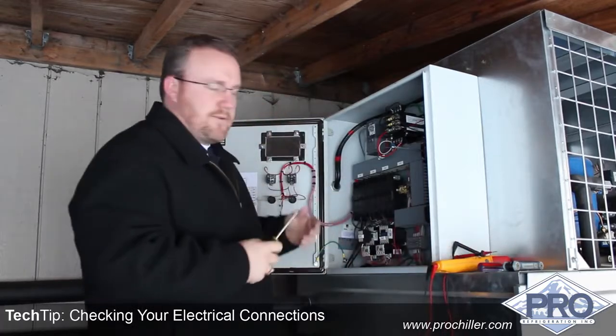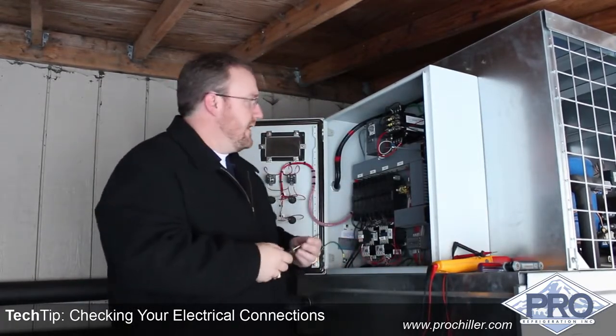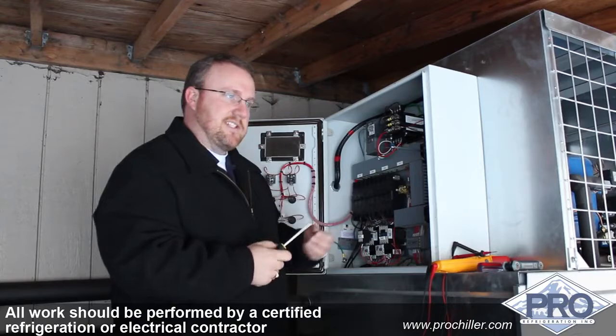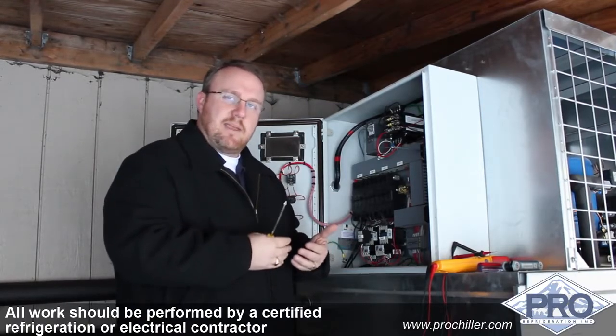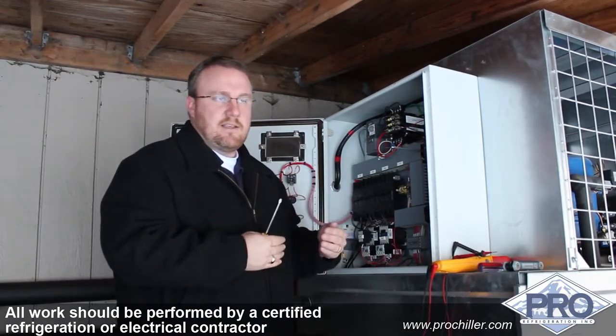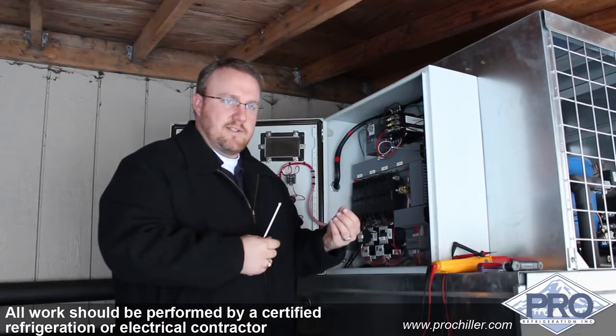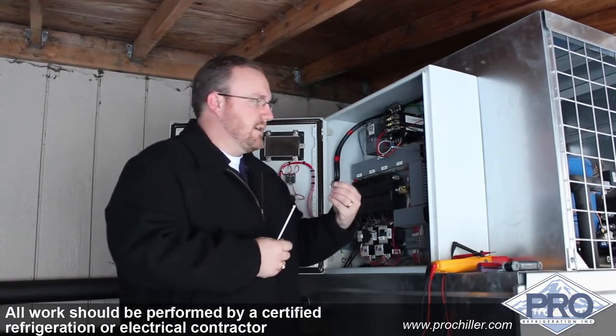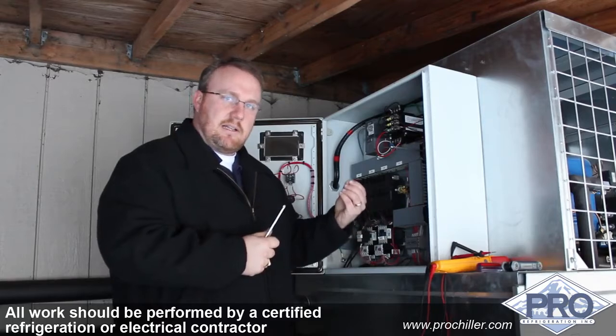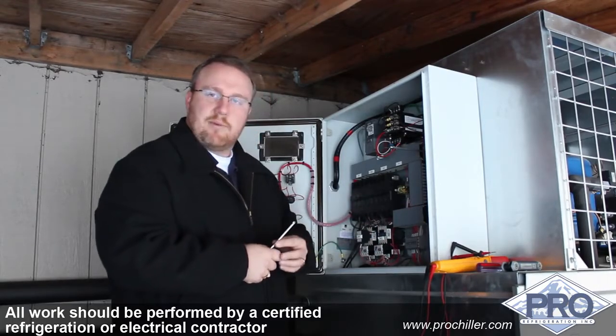What we like to do is go through once per year and make sure that all the electrical connections haven't loosened. There can be a tendency from heat to make the copper wires get a little soft, which will then lead to a loose connection and could lead to higher amperage.